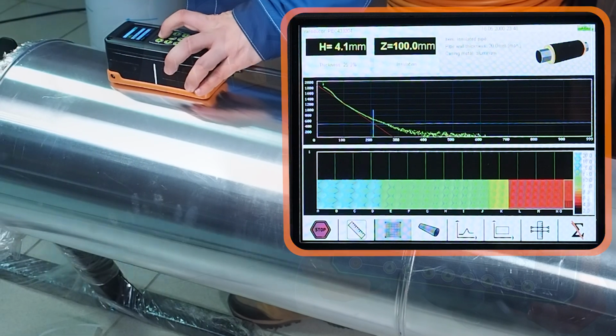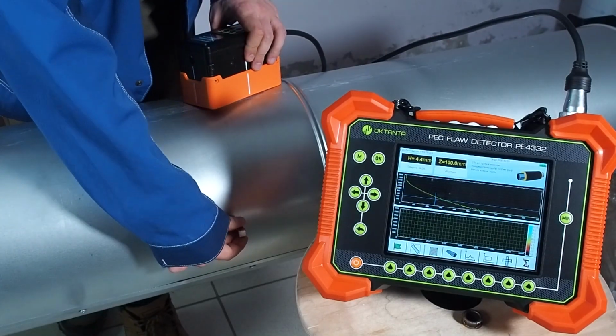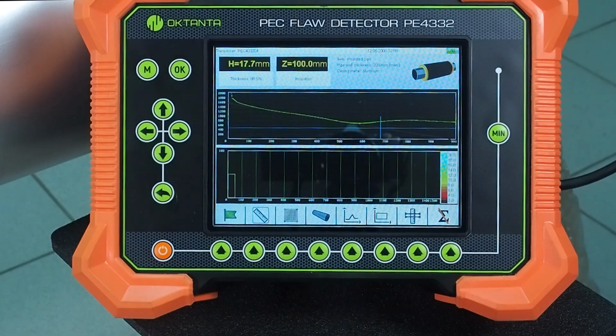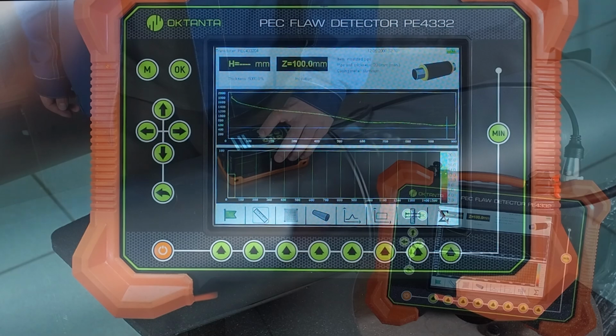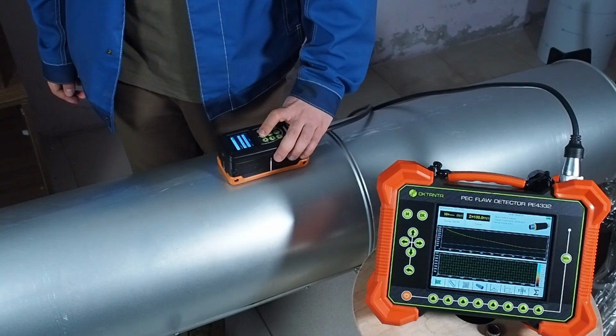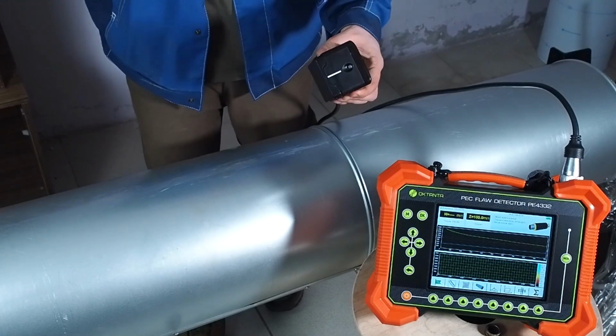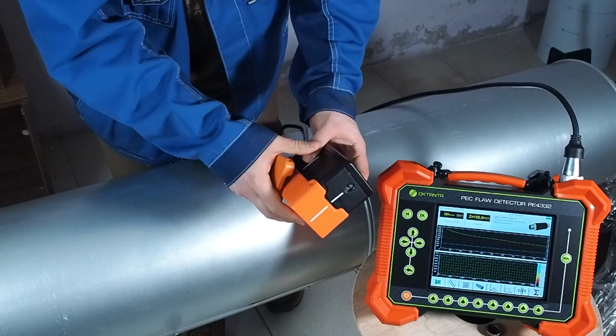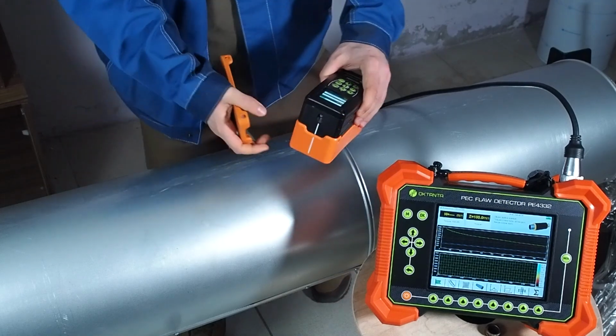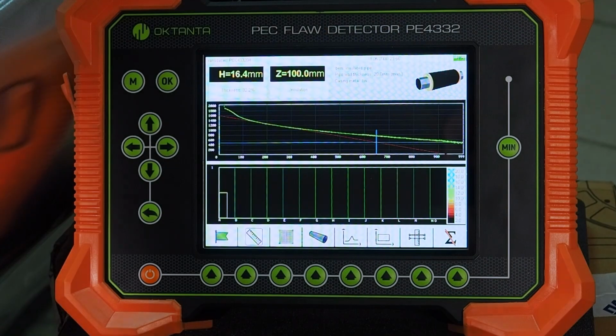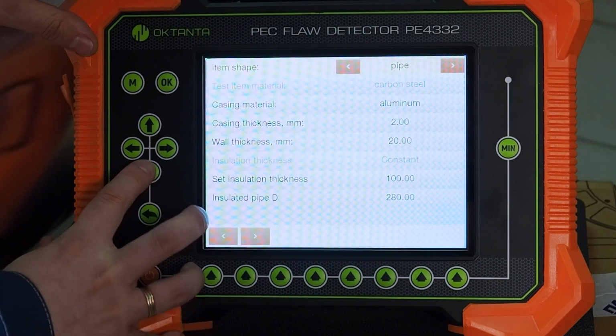Let's complicate the task and install a galvanized casing. We see that the casing magnetizes, which means that it will confuse readings of devices based on electromagnetic effects. In our case, the distortion resulted from the acoustic effect, which we can dampen using a special cap. When calibrating, do not forget to specify that the casing is made of galvanized steel.